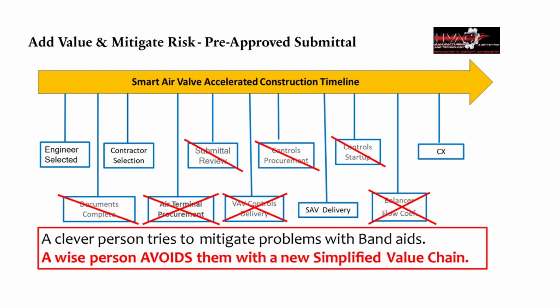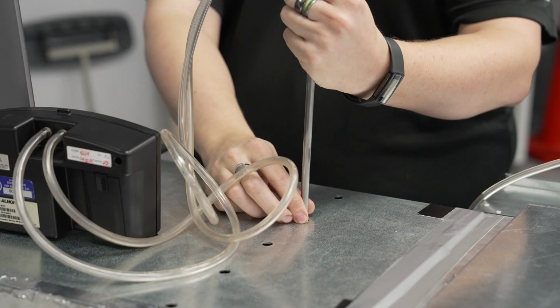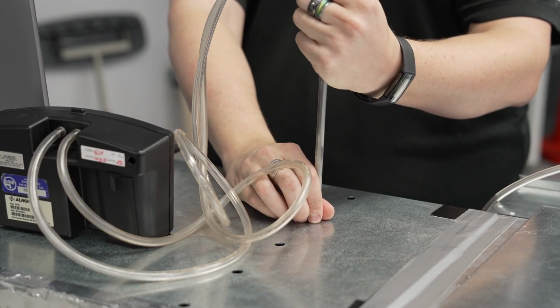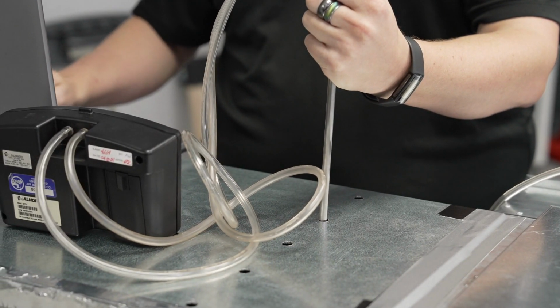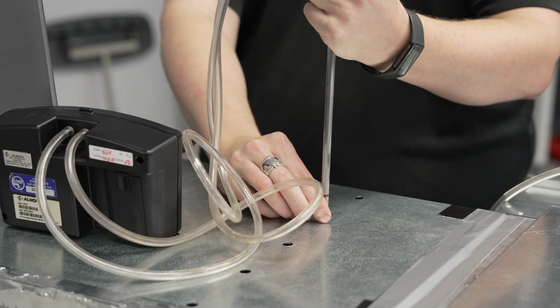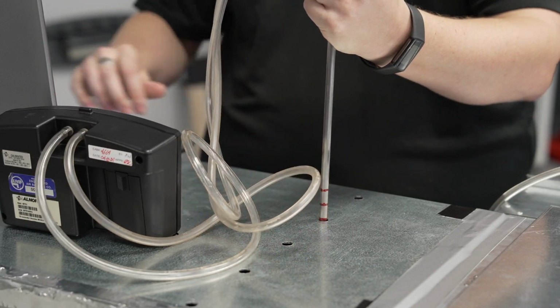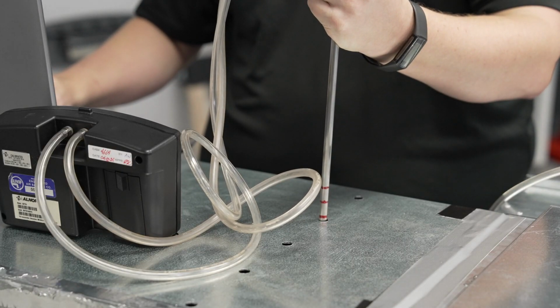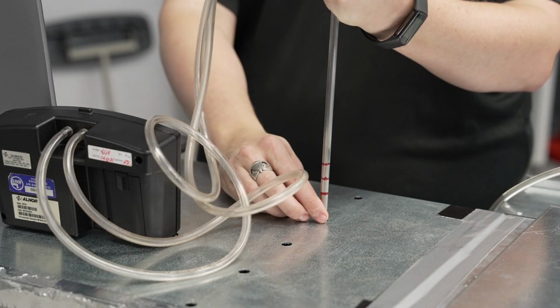The SAV allows for an accelerated construction schedule, resulting in a faster infrastructure monetization as a single-size unit is used at all the zones due to the 100-to-1 turn-down ratio. With the SAV, you have a future-proof infrastructure with no mechanical upgrades when reconfiguring workspaces. The SAV has been third-party tested with state-of-the-art airflow stands, comparing flow stand results, traverse results, and capture flow hood results. It was found that a factory-calibrated capture flow hood can be off by 10% or more.